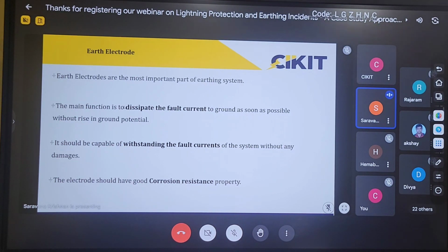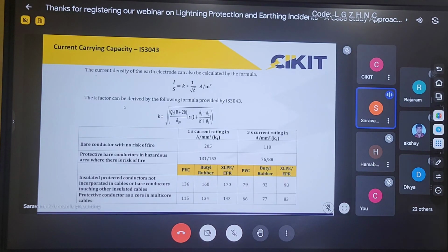the conductor will melt. So the standard has provided the formula for calculating the current carrying capacity. So this is the formula. From this you can observe that I is equal to S K by root T. So the three parameters involved are the cross-sectional area S, the constant K, and the third one is the duration T. So whenever we are mentioning the fault current, we should always mention it with the duration. For example, 20 kA for 1 second, 25 kA for 3 seconds, 40 kA for 1 second. So the fault current should be mentioned along with the duration, because depending upon the duration, the fault current withstand level also will be changing.